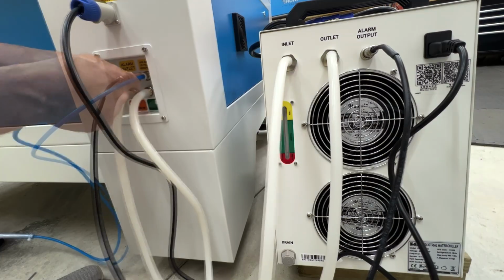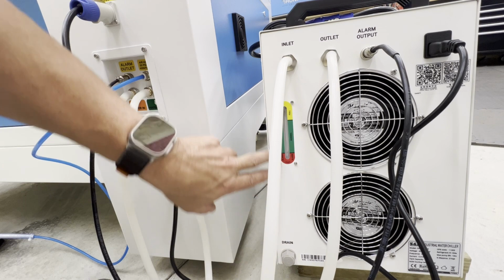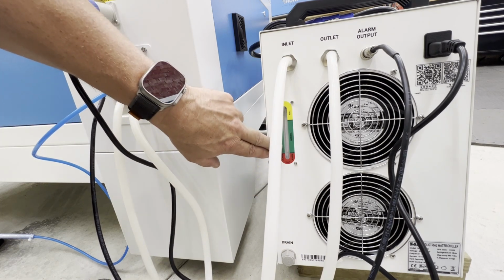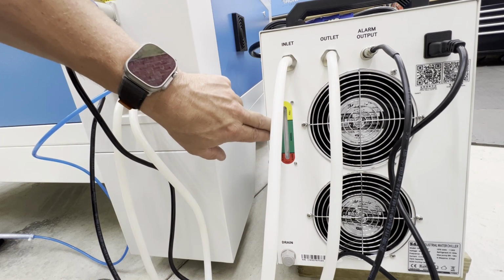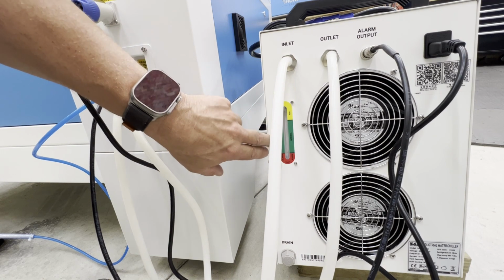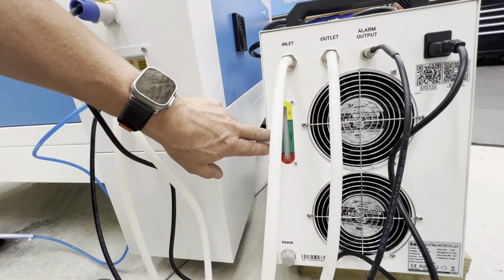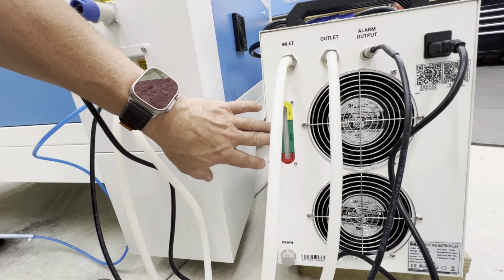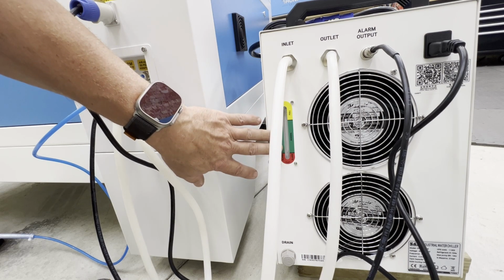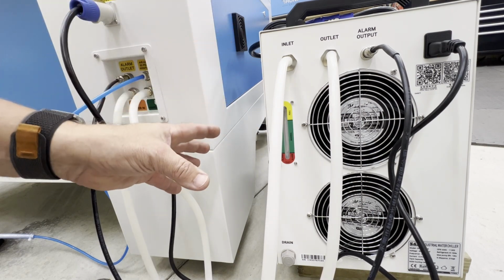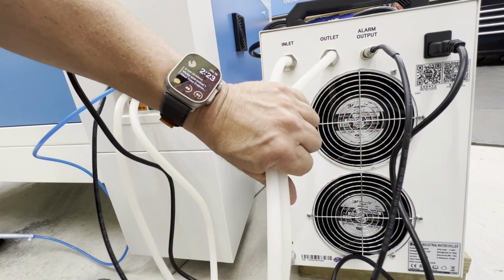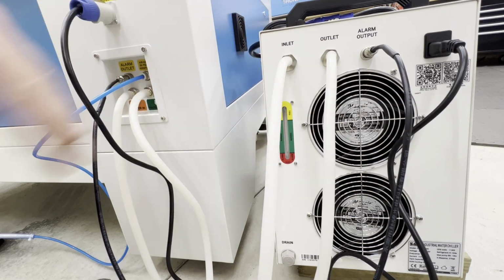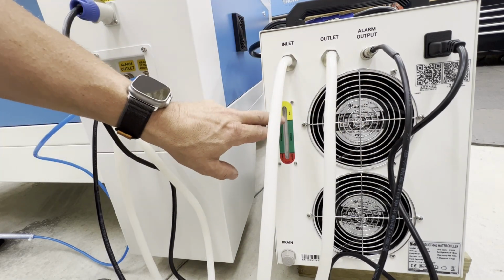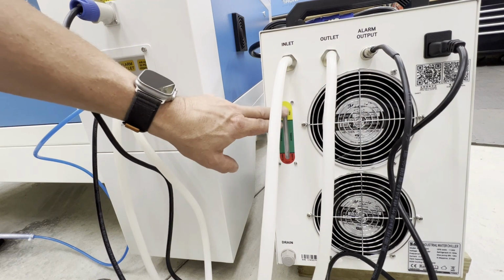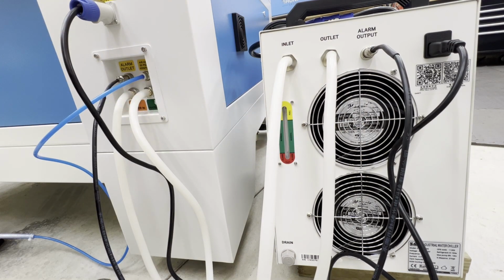On the chiller, we have our drain, and our glass window for sight of whether the water is low or filled. Typically I'll put about a gallon, almost two gallons, of distilled water into the chiller, check it, turn it on, let it run a bit to get all the water into the hoses and the tube, and then top it off to make sure it's up to the full line. Anywhere in this yellow area is a good spot to be.